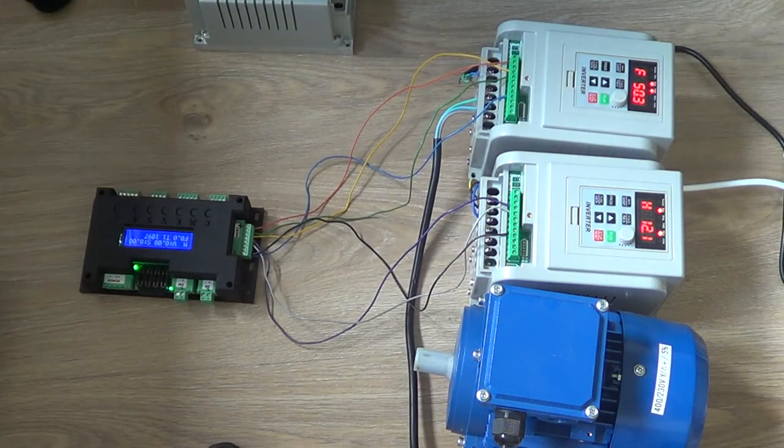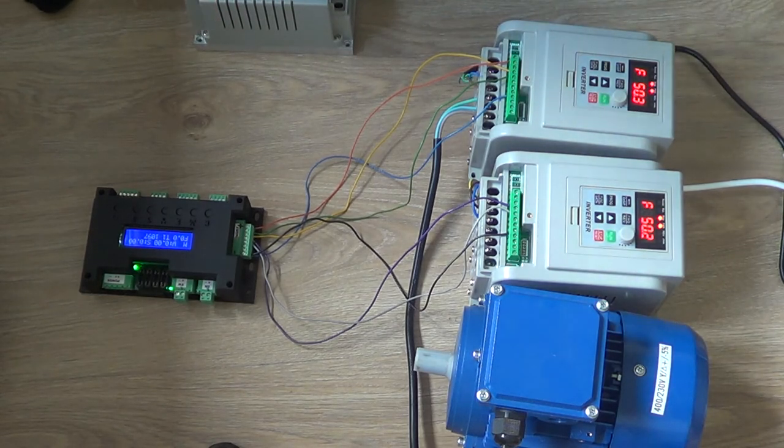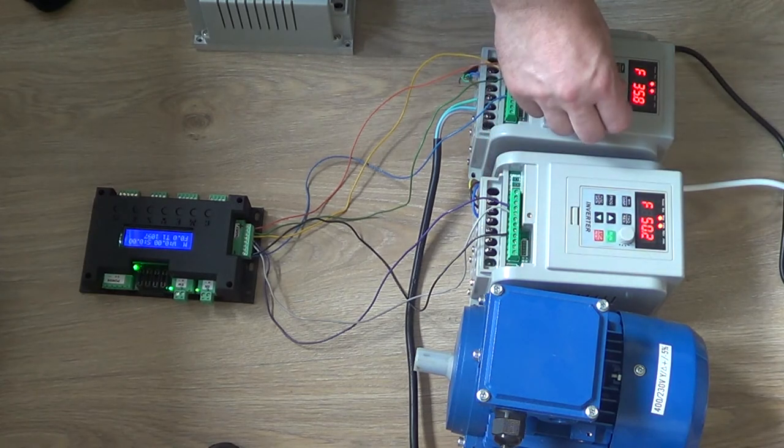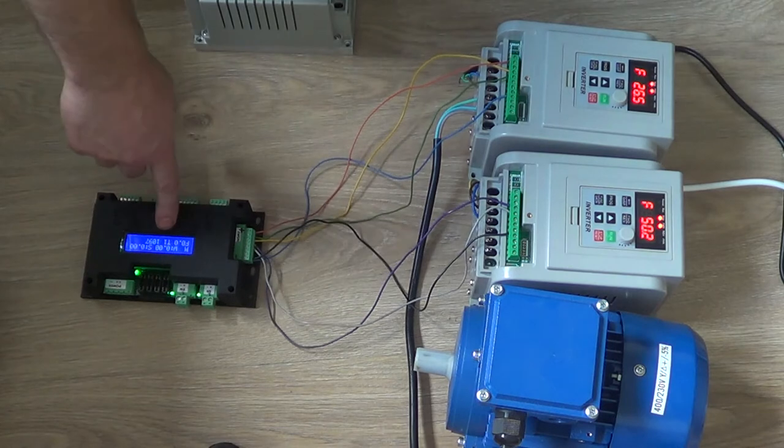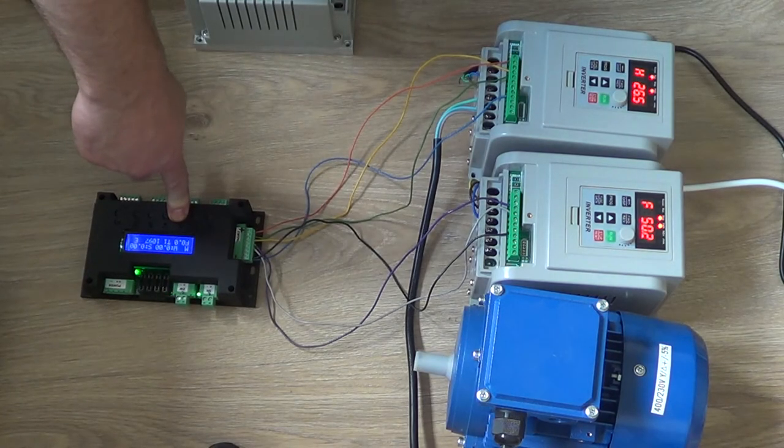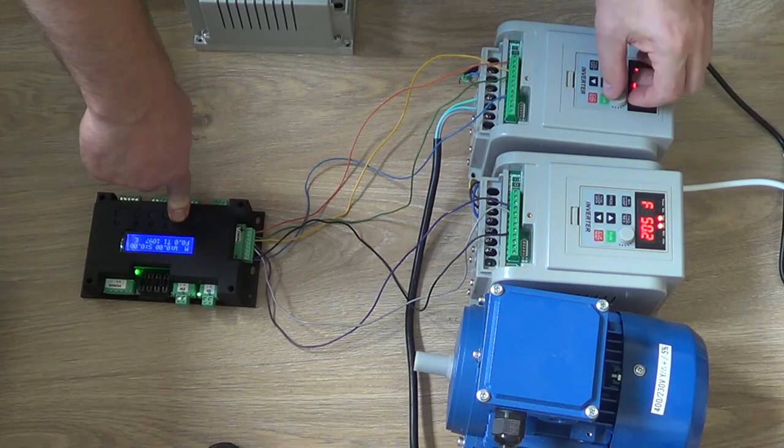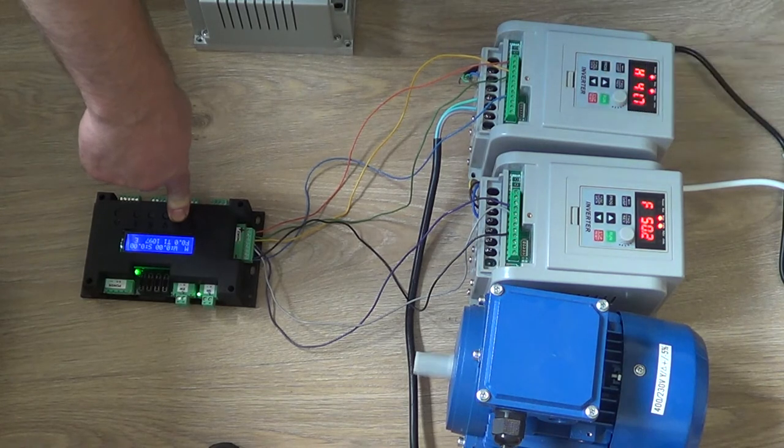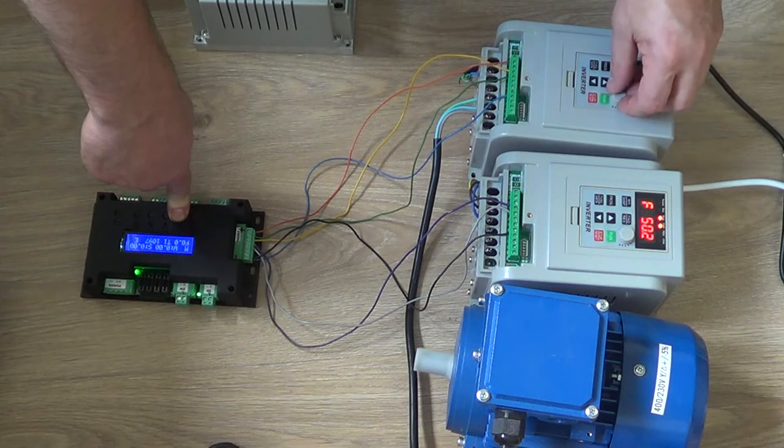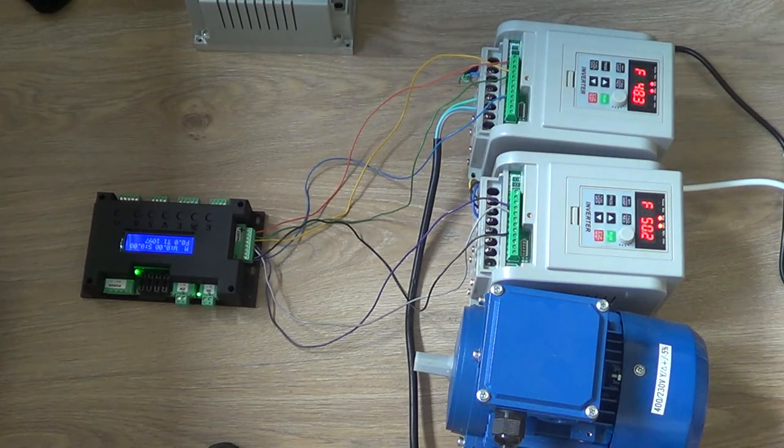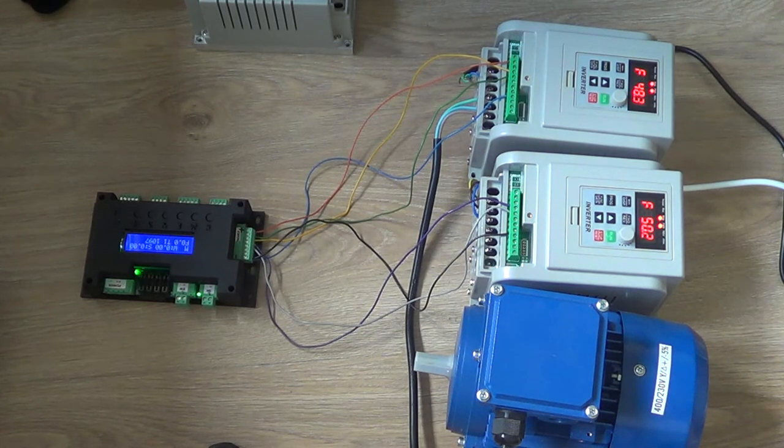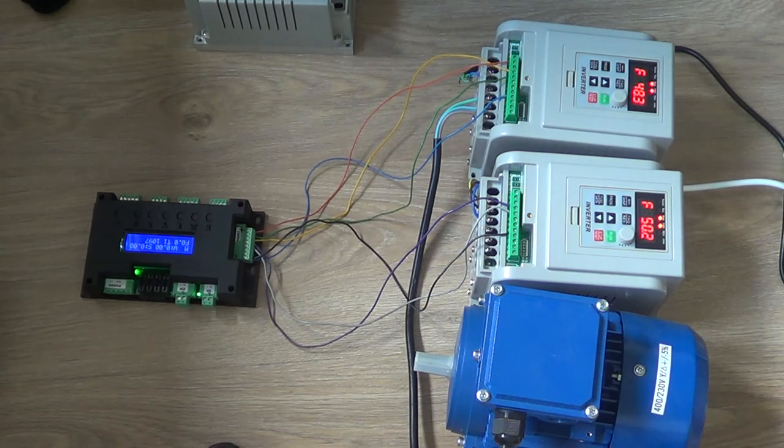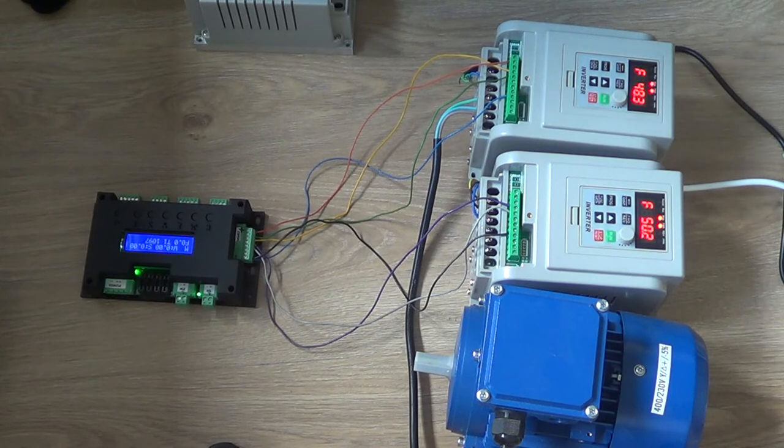So I can just change the direction through the controller and of course I can just change the speed of the engine, of the motor, by the frequency. So now it's gonna be moving up to 26 hertz, 40 hertz, 50 hertz, right? So I can just easily manage my device if I do have any problem with the speed of my tracker and the construction is not prepared enough. I just can use the inverter and that will be much easier to manage it.